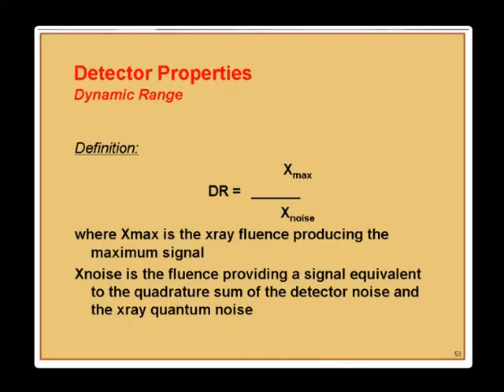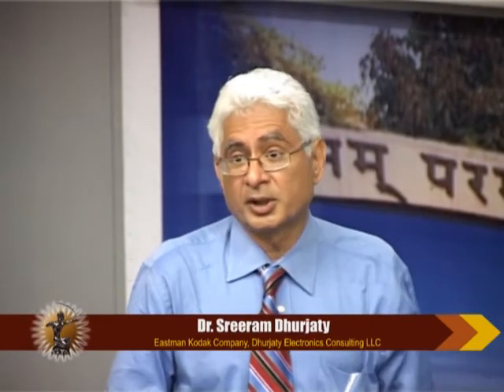If you have detectors that are sensitive to different energies, you could actually overlap them. The dynamic range is a ratio where X-max is the X-ray fluence producing the maximum signal, and X-noise is the fluence producing a signal equivalent to the quadrature sum of the detector noise and the X-ray quantum noise.